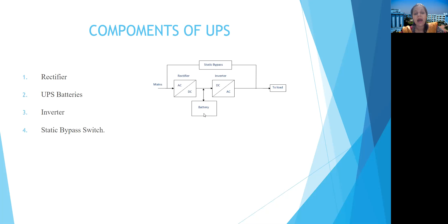Now, what are the components of UPS? Within a UPS, what are the devices it must have? It must have a rectifier, battery, inverter, and static bypass switch. This static bypass switch is also known as an anti-parallel switch. The connection I will show you later. The static bypass switch can also be termed an anti-parallel switch. This is the basic block diagram of a UPS, where a rectifier circuit, inverter circuit, battery, and static bypass, these four components, are used.